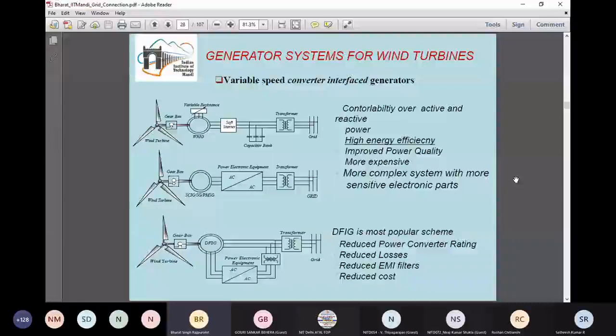Let's talk about the first, uppermost left-hand side scheme. This is based on a wound rotor induction generator. A variable resistance is connected in the rotor, which is wound rather than squirrel cage, and by varying the resistance, the speed of the system can be controlled. What is the advantage of this variable speed? We will discuss that in the next slide, but here we are just seeing how the speed can be varied. Then once again, a capacitor bank is there to provide reactive power support.